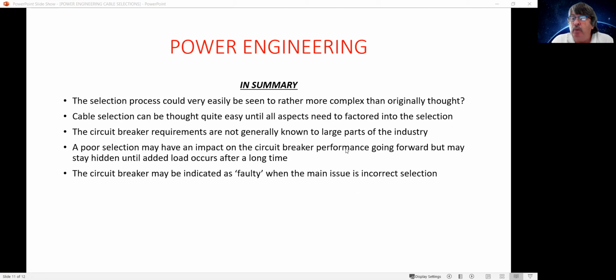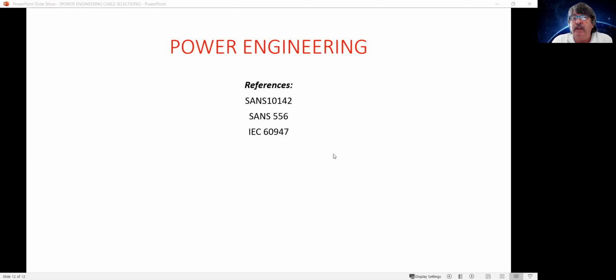But because they work on thermal, they have to have regard for thermal variation, if it varies from the ideal of the circuit breaker, which is the ideal from the actual calculations it's based on. These references come from the SANS wiring code 556, which is a circuit breaker specification, and the IEC equivalent, which is exactly the same for circuit breakers, 60947. Thank you very much. I hope this doesn't make it more complex going forward, but gives you some idea that we're getting to a point where we've got to add a few other extras in.